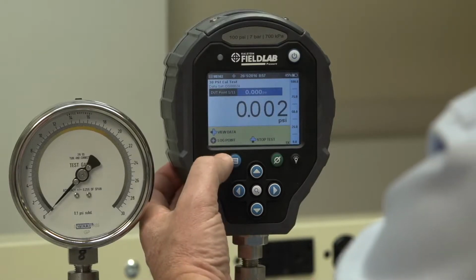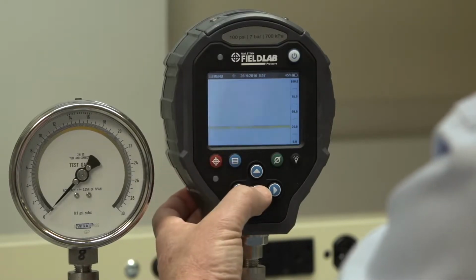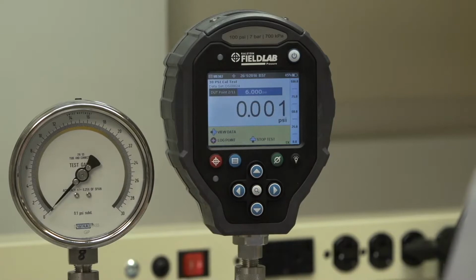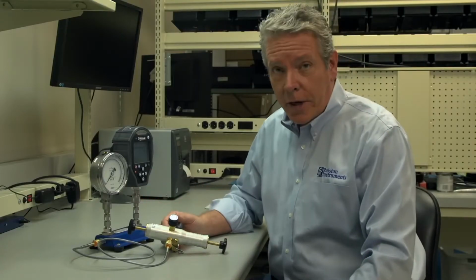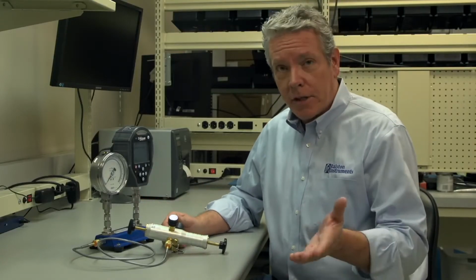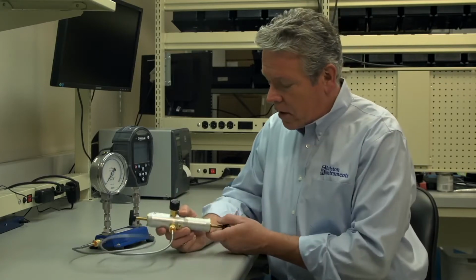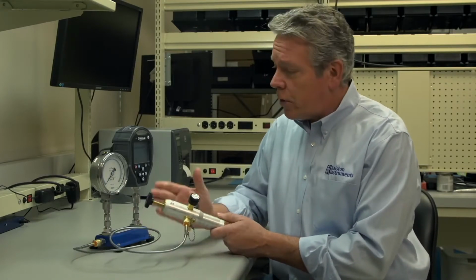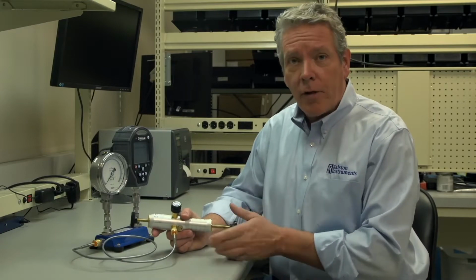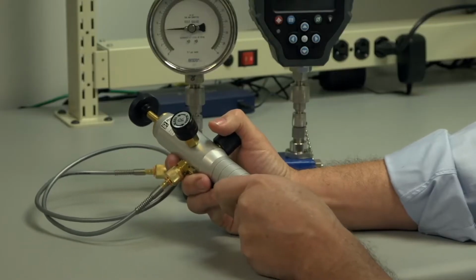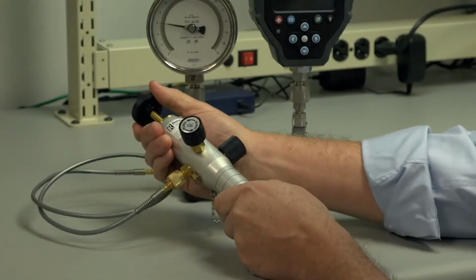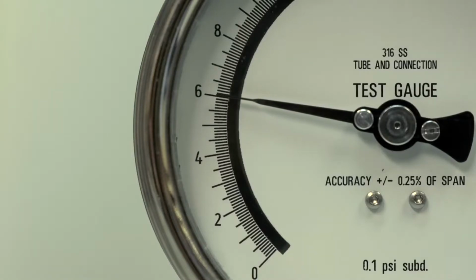So we'll press log, then accept. And the data point is logged. And the FieldLab moves on to prompt you for the next test point, in this case 6 psi. Now we'll apply pressure to achieve a reading of our cardinal point on the device under test. And then we'll precisely dial it in with the vernier so our needle falls exactly on 6 psi. And since it does fall on a major hash mark, it makes the setting much easier and more accurate.